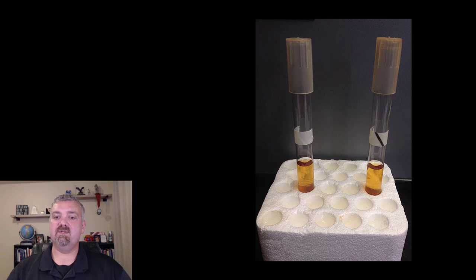Alright, so how do you know an autoclave is going to work? Here we see autoclave tape, it's the simplest way to use it. That black stripe will form on that piece of tape if it reaches the temperature you need, the 121 degrees.